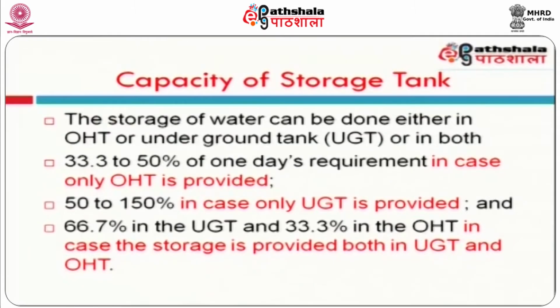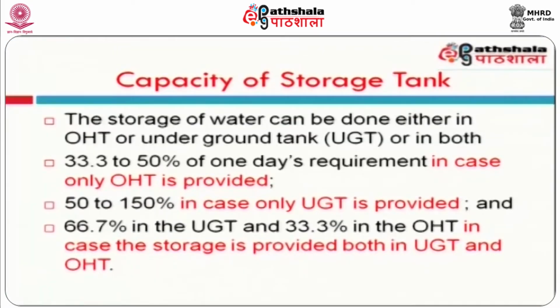If you are storing water in underground storage tank and the overhead tank, then the underground tank, UGT, has a storage of 2/3, that is 66.7%, and the overhead tank will have 1/3 or 33.3% of the storage. Whether you are storing in the overhead tank or in the underground tank only, or both in the overhead tank and underground tank, we have to provide the storage capacity. In the storage tank, both the ground level tank and the elevated tank, we need certain requirements.